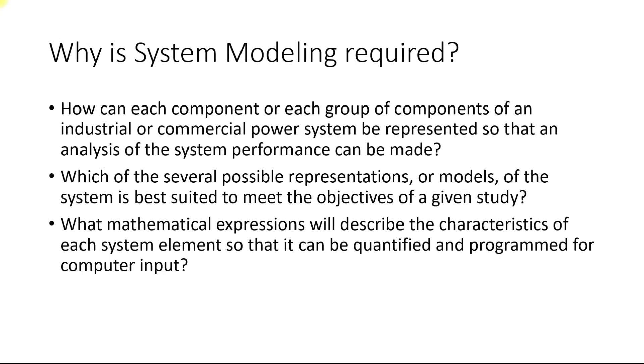Secondly, we need to choose which of several possible representations or models is best suited for the objectives of a given study. For instance, if you are performing a simple load flow analysis, you are not interested in the dynamics of a motor. Instead of detailed modeling, you can simply use the megawatt and megavar — active and reactive power — values.